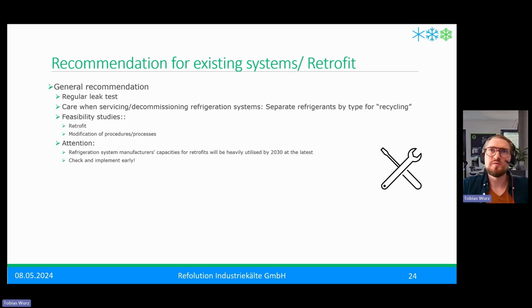Okay, for existing systems for retrofit, we have some general recommendations. That means do regular leak tests, even more than is needed or required in the F-gas regulation. Take special care when you do service or even decommissioning of a refrigerant system. Separate these refrigerants by type so you can recycle this refrigerant in other refrigerant units. And start feasibility studies now to look at retrofits of your units. Or you could even adapt your processes or procedures to some other kind of refrigerants.